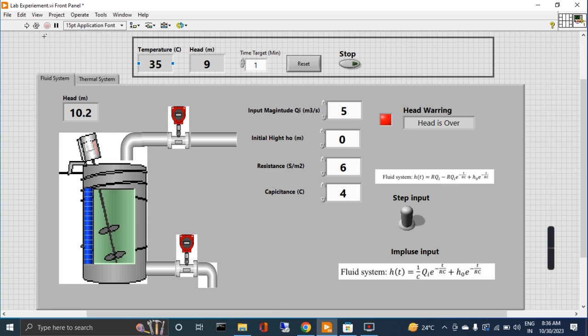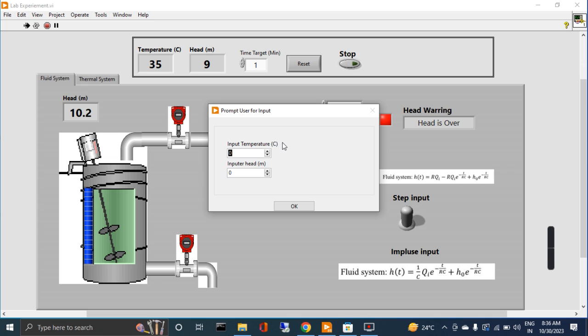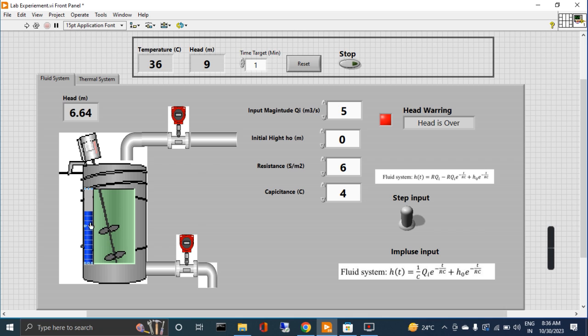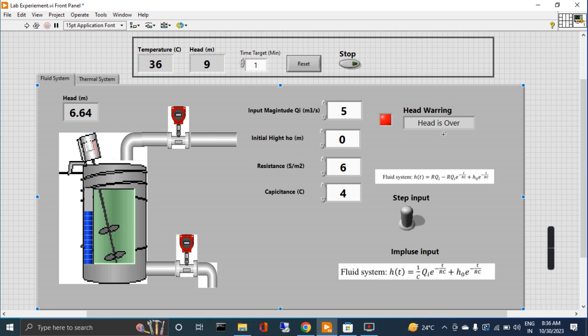If I give step again, let's say I give 36 for temperature and height is 9. Now see, this is increasing, and at 6.64 - this is actually 70% of the limit which I set initially - then the system gives you head is over alarm or warning.